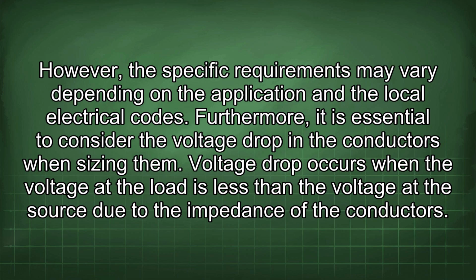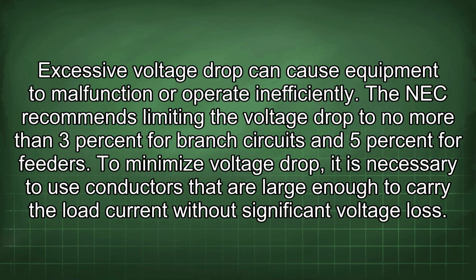However, the specific requirements may vary depending on the application and the local electrical codes. Furthermore, it is essential to consider the voltage drop in the conductors when sizing them. Voltage drop occurs when the voltage at the load is less than the voltage at the source due to the impedance of the conductors. Excessive voltage drop can cause equipment to malfunction or operate inefficiently. The NEC recommends limiting the voltage drop to no more than 3% for branch circuits and 5% for feeders.